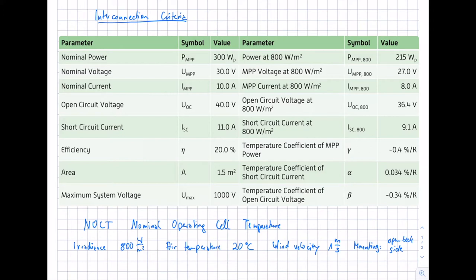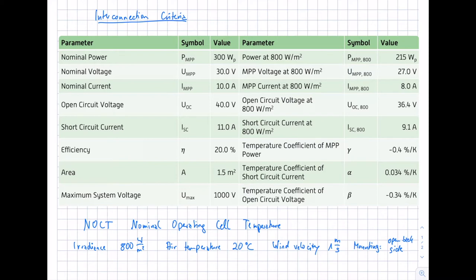The warmer the module gets, the less efficient it is, and the lower the voltage and power. We also have temperature coefficients for power, short circuit current, and open circuit voltage. These three values tell us how power, current, and voltage change with increasing or decreasing module temperature relative to the STC temperature of 25°C. For example, the temperature coefficient for open circuit voltage shows that an increase of 1°C reduces the voltage by minus 0.34%, and if the cell temperature is below STC, the voltage increases.